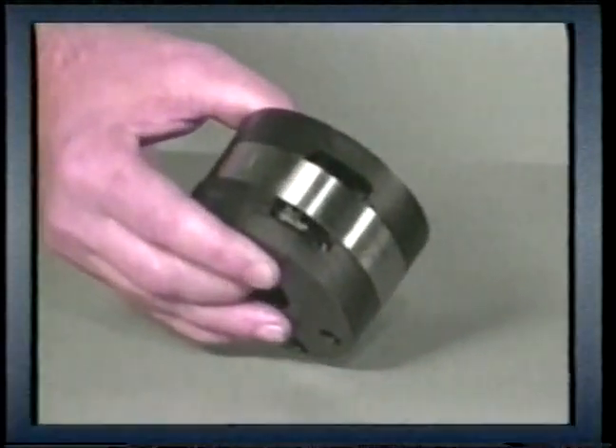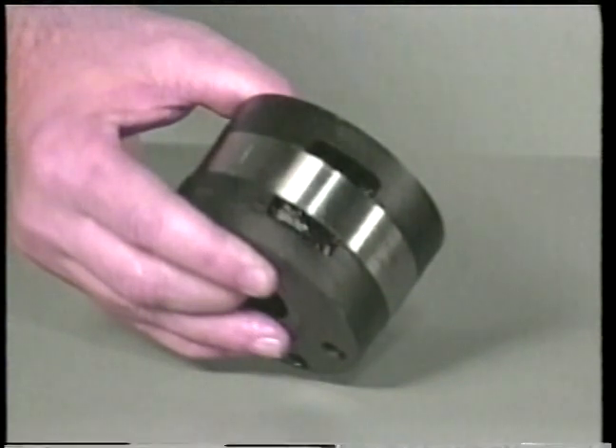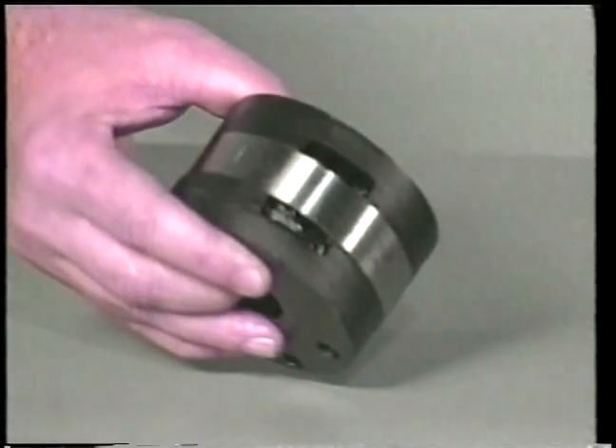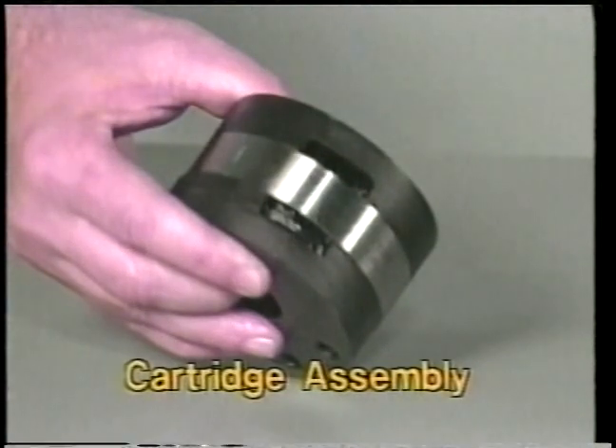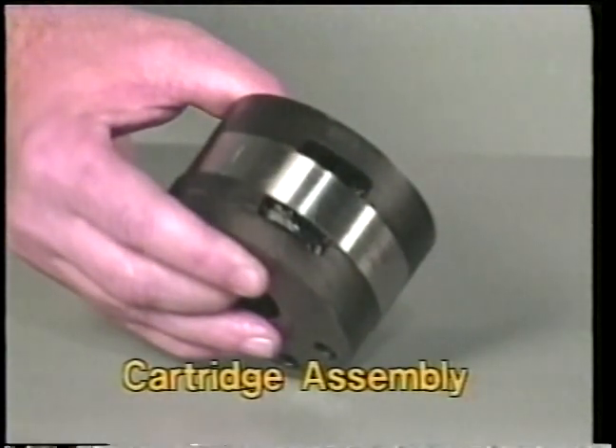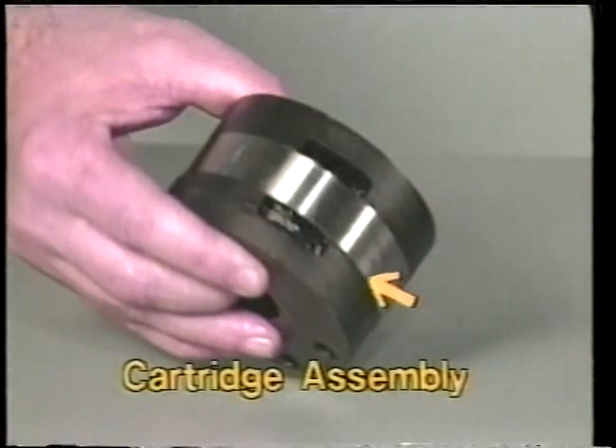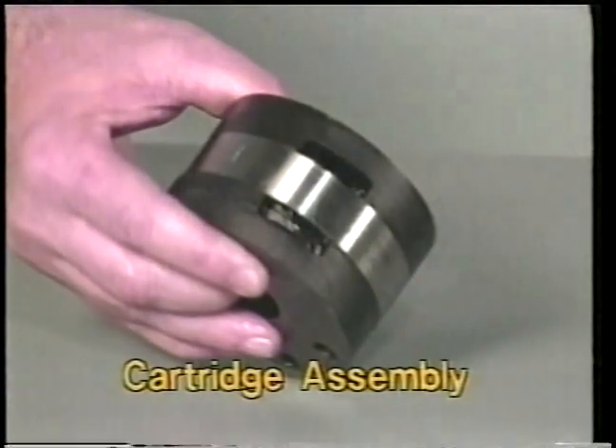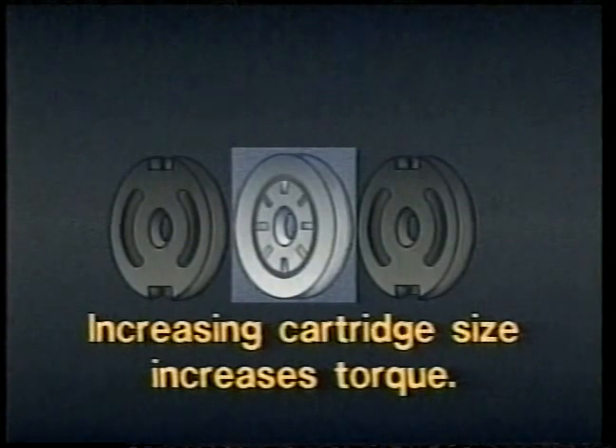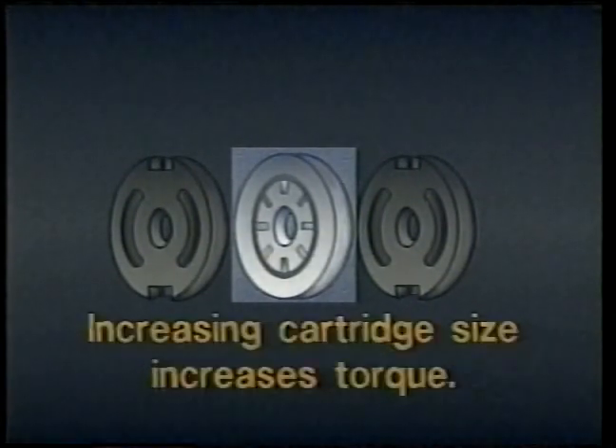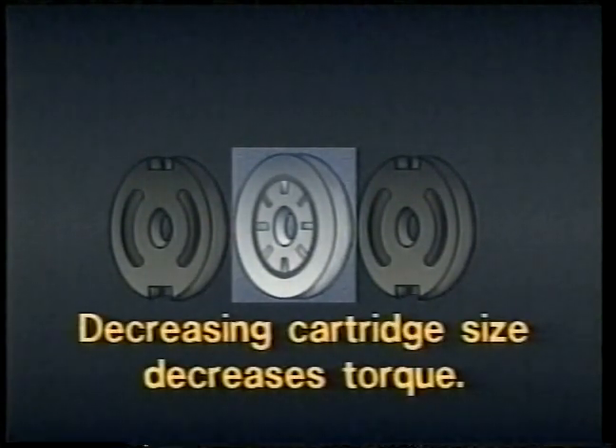The size of a motor means its displacement, or how much fluid it can hold. In a vane type motor, changing the displacement can only be done by changing the cartridge assembly, which is the rotating group and the cam ring sandwiched between the port plates. Increasing the size of the cartridge assembly without changing the pressure will increase the torque, because the vanes of the larger cartridge assembly have more area exposed to pressure. Decreasing the size of the cartridge assembly without changing the pressure will decrease the torque, because the vanes in the smaller assembly will have less area exposed to pressure.